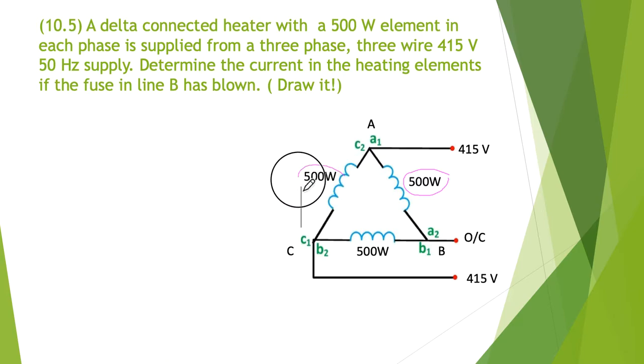And we've got 500 watts in each of the elements. It's an open circuit, so no current, no connection here. So what do we do next? So there is no phase relationship here. Root three is a waste of time. We have to use straight Ohm's law.